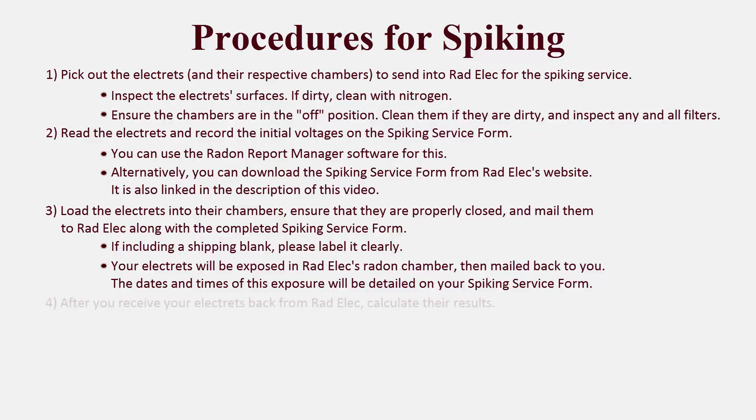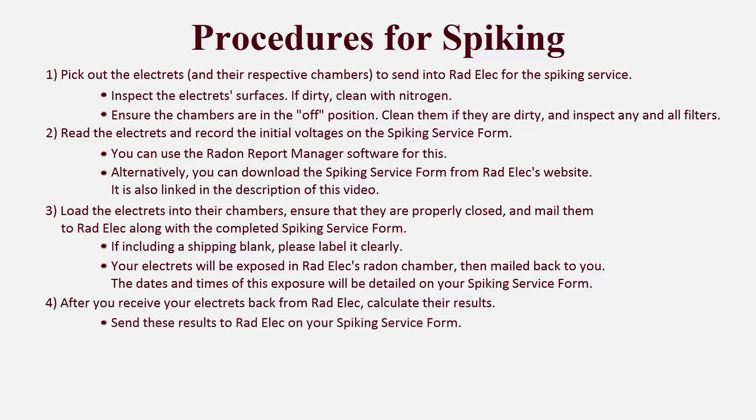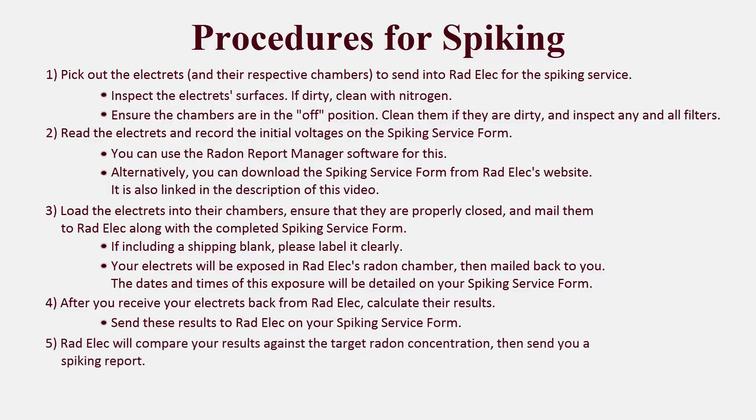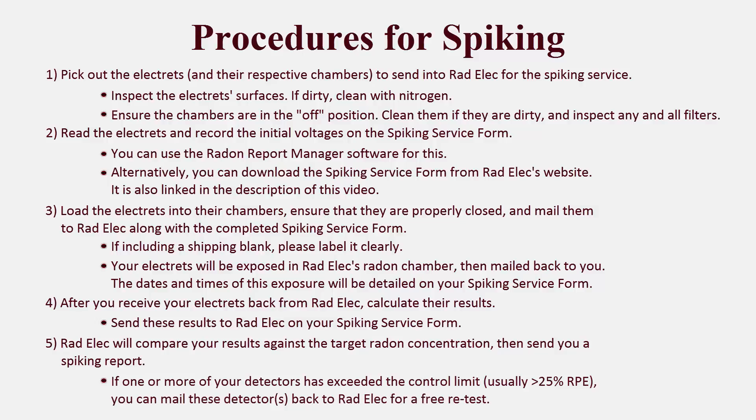And this takes us to step four. After you receive your electrets back, calculate their results — you can use the Radon Report Manager for this step. After you've calculated their results, send them back to us on your spiking service form, usually via email or fax. The fifth step is when Radelec compares your results against the known target radon concentration. We will email you a spiking report so that you can see how accurate your results are. If one or more of your detectors has exceeded the control limit, which is usually greater than 25% relative error, Radelec will offer you a free retest.